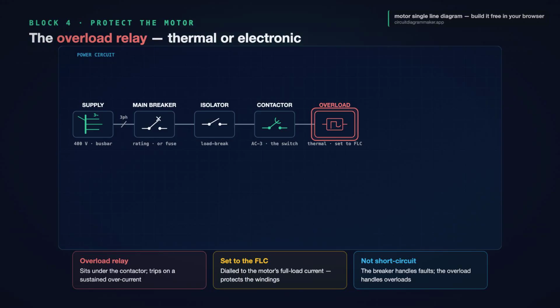And it is set to the motor's full load current, the FLC, so it protects the windings without nuisance tripping on a normal start. Breaker for faults, overload for overloads. Two different devices, two different jobs.